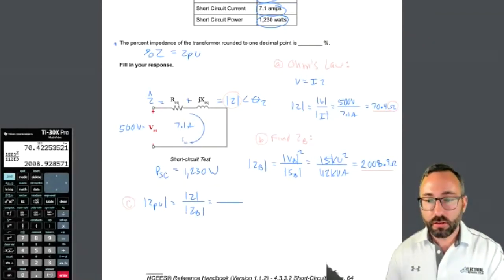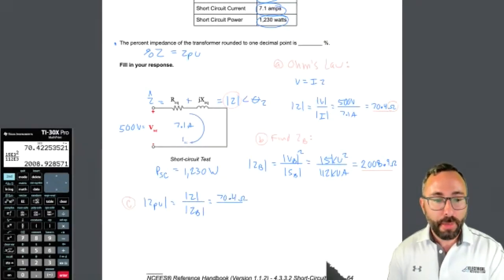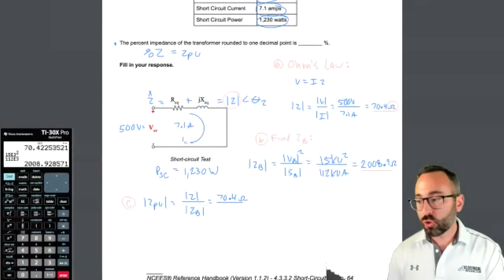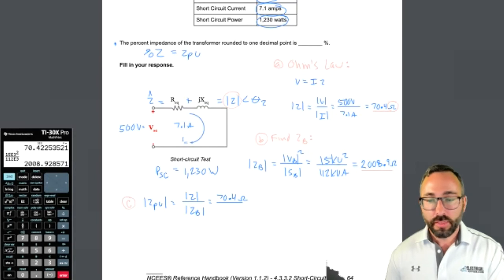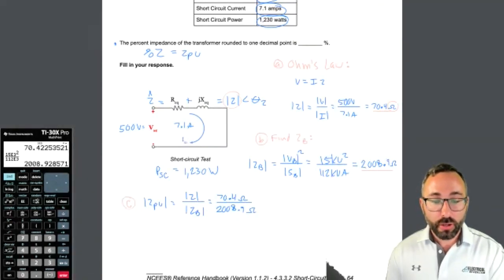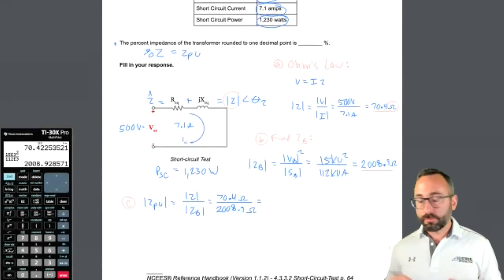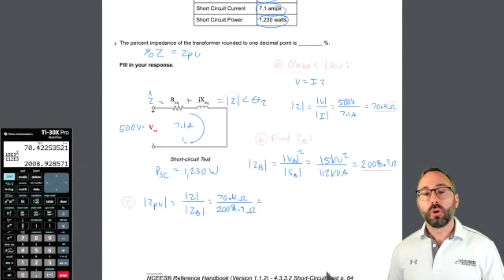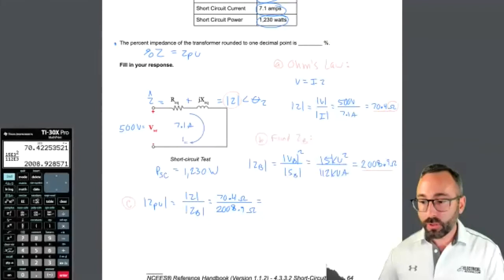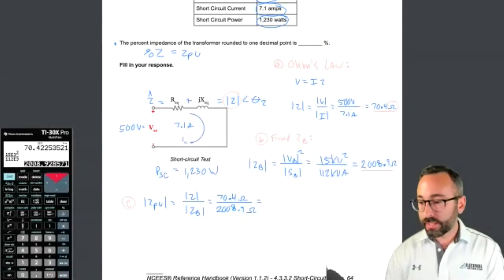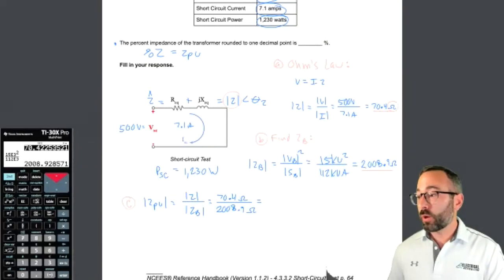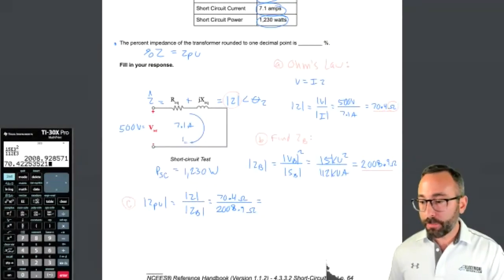I'm going to divide right here, 70.4 ohms. That's the magnitude of the transformer series winding impedance. I'm going to divide it by the base impedance, 2008.9 ohms. All right, now here's where the fill in the blank problem gets tricky. Got to be as accurate as possible. We don't know the margin of error or the tolerance that they're going to accept. So I'm going to go in my calculator. I'm going to scroll up, pressing the up button until the 70.4 is highlighted. I press enter to bring it back down.